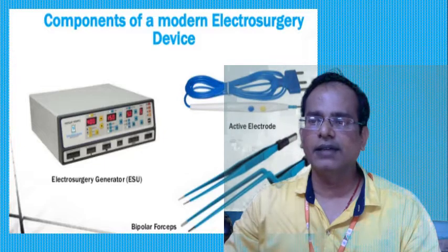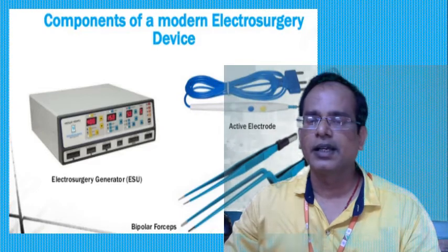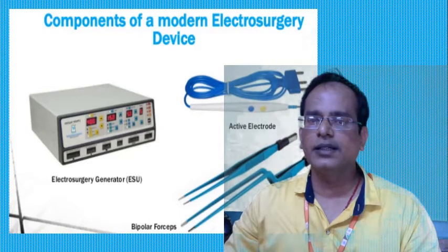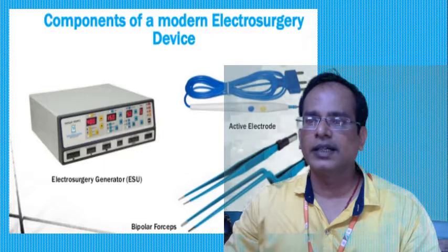It has the ability to cut precisely with limited blood loss. That is a very important feature of the electrosurgery machine. It produces limited blood loss, not heavy, and it is used in all general surgical procedures. For example, dermatological, gynecological, cardiac operations, plastic surgery, ophthalmic procedures, spine-related surgery, ENT, and maxillofacial surgery also use surgical diathermy.